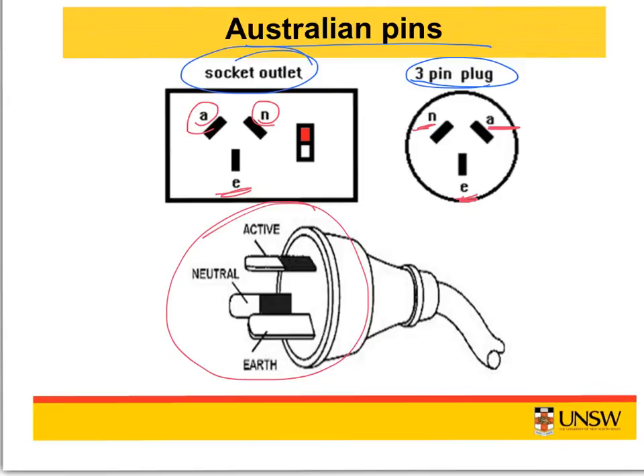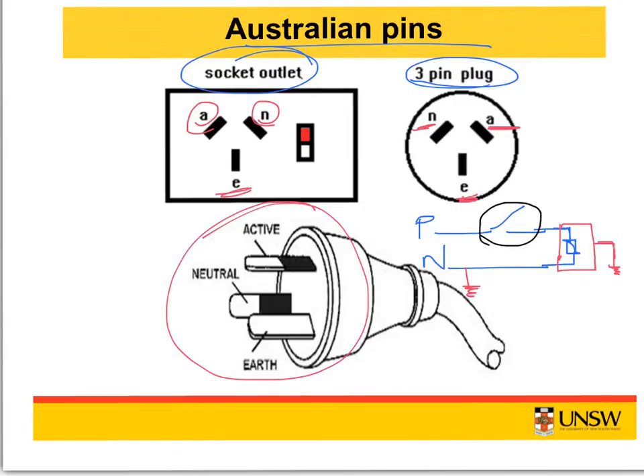So if you take the diagram, let's say the phase wire goes through the switch and the neutral wire goes directly to the equipment. So if you see, this is a load, and this is the external casing of the load. And this external casing of the load is earthed here, and the neutral is also earthed. Now here you have the circuit breaker, which is a switch. So the neutral wire is grounded at the terminal box. So this is the grounding of the neutral wire at the terminal box in the house.